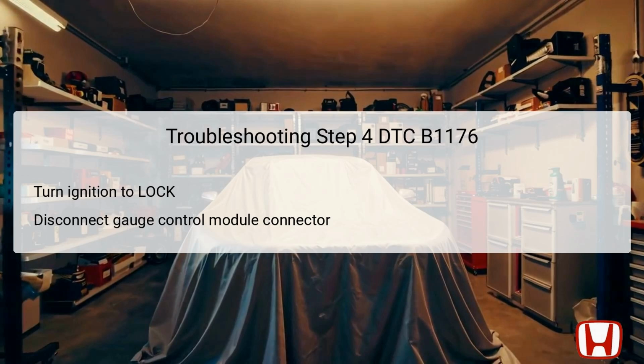After disconnection, the technician can systematically check for continuity and ensure that the correct flow of signals is maintained without obstruction or faults. This is critical in pinpointing whether the gauge control module itself is faulty or if the issue is rooted elsewhere in the wiring or connection.